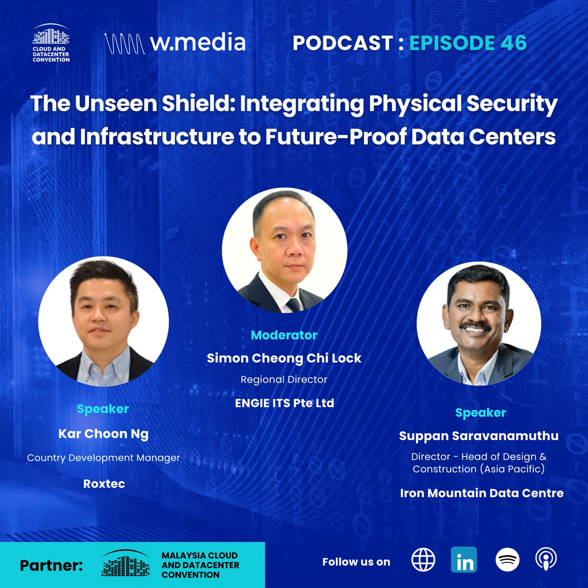I think liquid cooling is the best one now. You can see a lot of booths on liquid cooling. Previously when we started as a data center, we all managed 3 kilowatt per rack, then 5, 8, 10. Now everyone is talking more than 30, 50, now 100, 125. So it's very difficult to cool that kind of high density server racks by air cooling, we don't have that kind of air. So definitely they will go with liquid cooling. But they still need air cooling also as a part, something like 70% liquid cooling and 30% air cooling, because they need air cooling for the network parts, network switches, all those things.